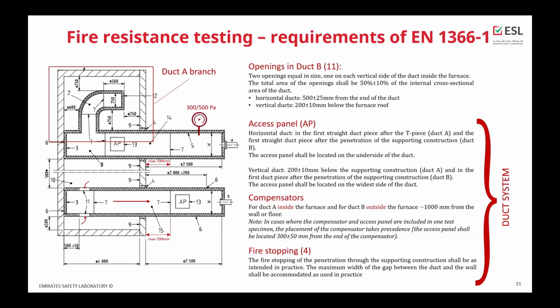EN is also defining the position for the access panel within the standard text. So it is describing accessories of the duct system and where these accessories must be placed within the duct, and it also says that the fire stopping shall be as in practice, with the maximum gap between the duct and the wall.